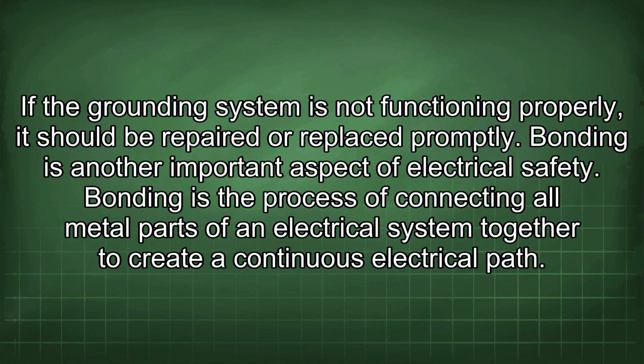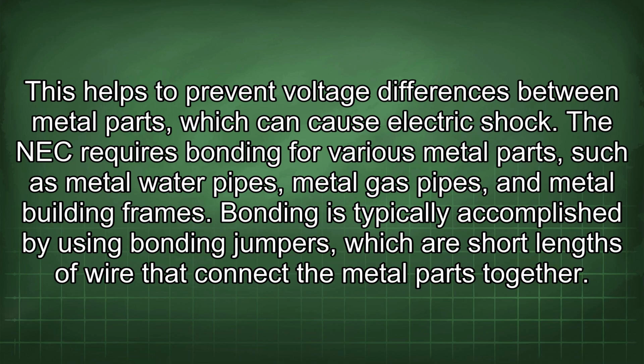Bonding is another important aspect of electrical safety. Bonding is the process of connecting all metal parts of an electrical system together to create a continuous electrical path. This helps to prevent voltage differences between metal parts, which can cause electric shock. The NEC requires bonding for various metal parts, such as metal water pipes, metal gas pipes, and metal building frames.